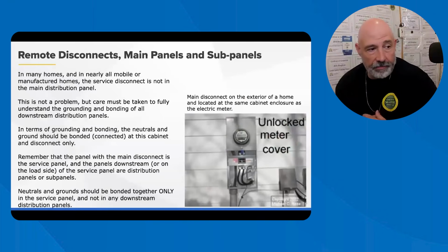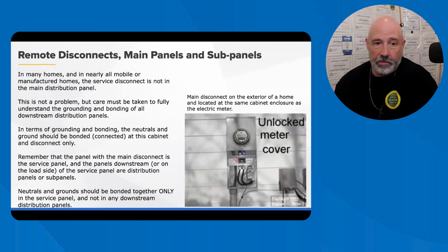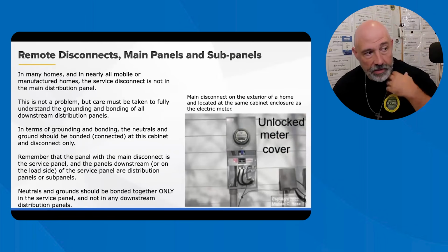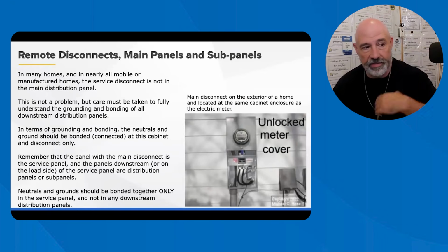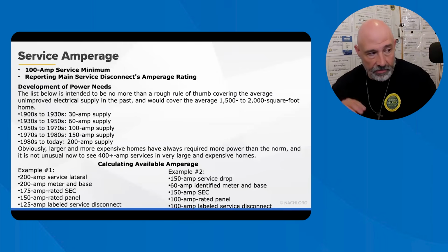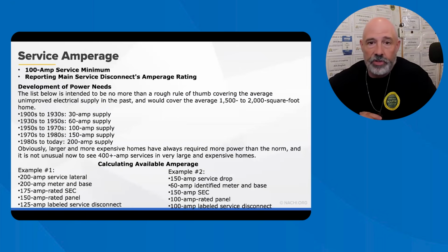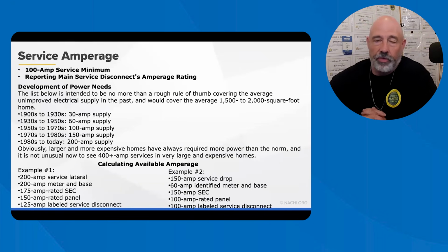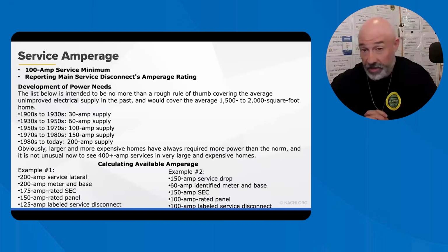This here is the meter box, and this actually needs a cover. You don't want to be able to stick your fingers in there or have an animal stick their tongue on it or something. You know, you don't want that. So you want to see the main disconnect on the outside. Make sure that it is good. For houses serving one family, the ampacity of the ungrounded service conductor shall be a minimum of 100 amps nowadays. A lot of times in the older houses, you'd see 60 amps.